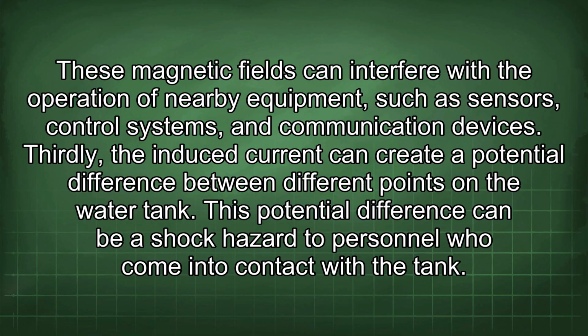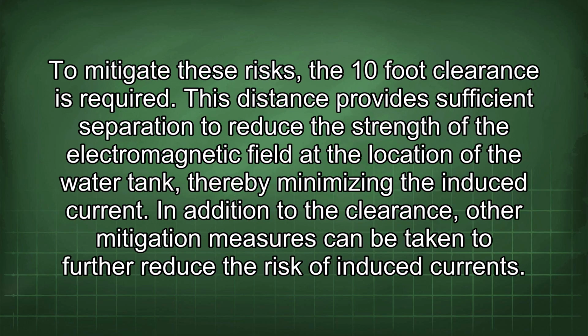Thirdly, the induced current can create a potential difference between different points on the water tank. This potential difference can be a shock hazard to personnel who come into contact with the tank. To mitigate these risks, the 10-foot clearance is required. This distance provides sufficient separation to reduce the strength of the electromagnetic field at the location of the water tank, thereby minimizing the induced current.